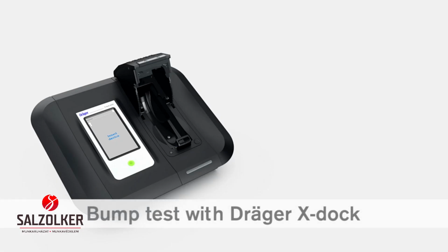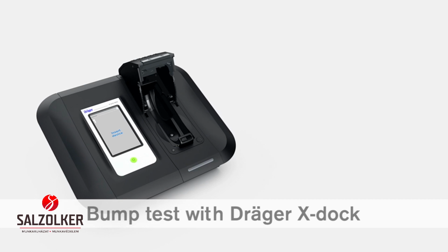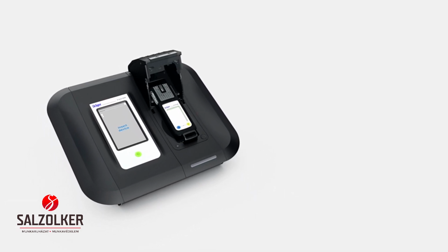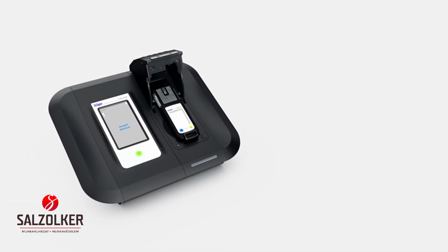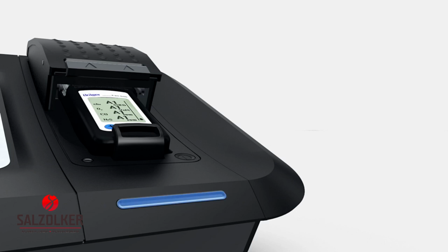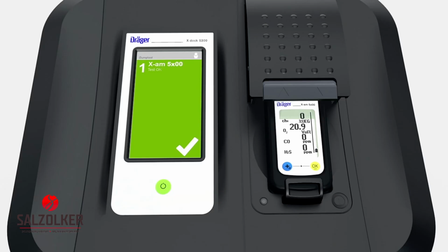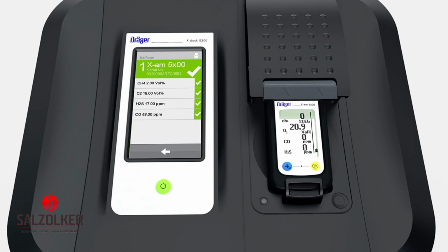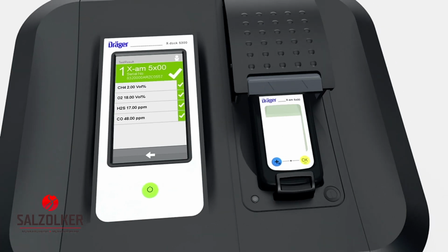You can also use a Dräger X-Dock station to perform a function test. Insert the device into the module. When inserted for the first time, X-Dock recognizes the device and automatically adds it to the integrated database. The LED strip will flash blue for the duration of the test. When the LED changes to green, the test has been completed successfully. The X-Dock screen also turns green. Touch it to obtain additional information on the test results. Now remove the device.